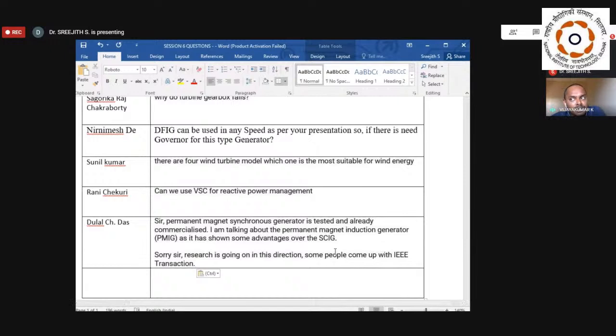Whether it's fixed speed or variable speed, if you go with a variable speed wind turbine, power electronic converters will be there. For higher capacity machines, you can prefer the PMSG and DFIG. For small scale wind turbines, 5, 10 or 15 kilowatt, permanent magnet synchronous generators are the best candidate.